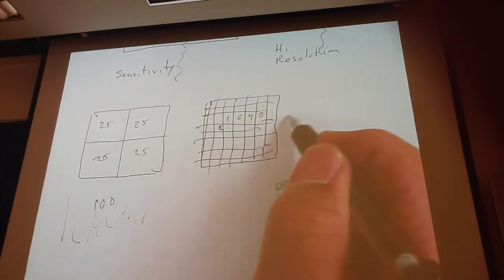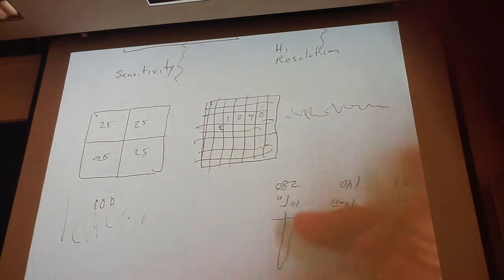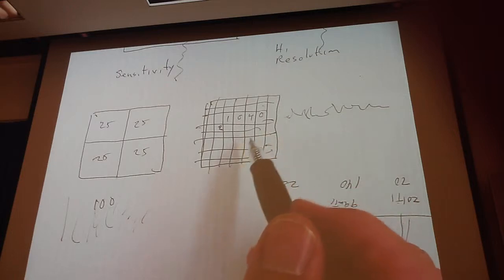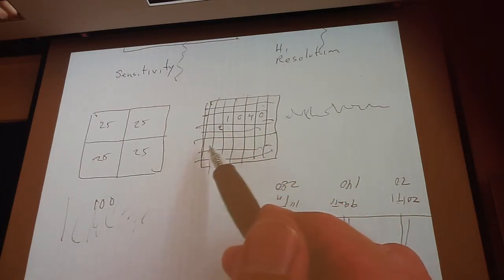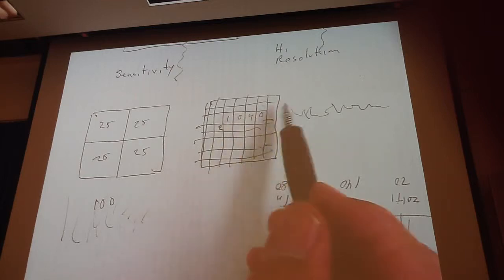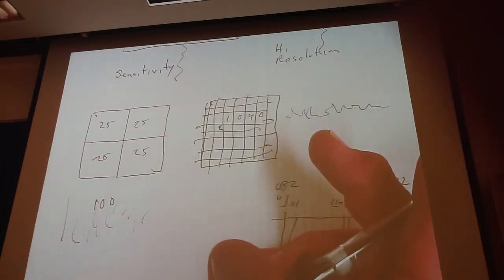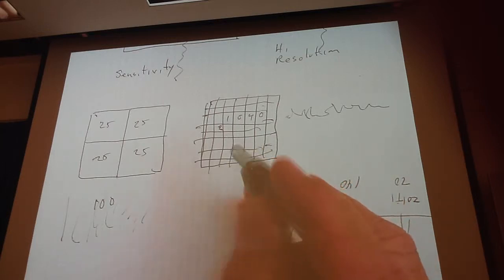And so what happens is you get a real grainy looking image that is more difficult. So that's why whenever we do uniformity correction, or I do SPECT imaging, we use a larger matrix, because we want to avoid the noisy image or the grainy image and have more uniformity from low statistics. Do you guys get pretty low statistics when you do a SPECT heart? People are shaking their heads, no! 64 by 64 matrix.